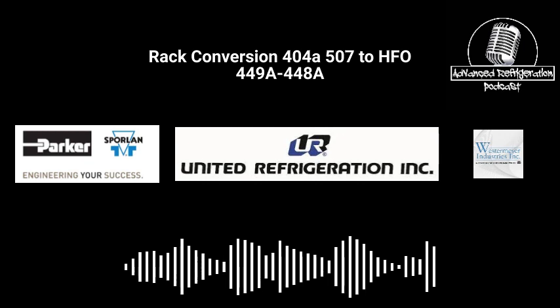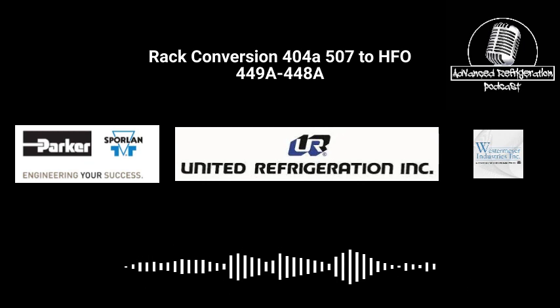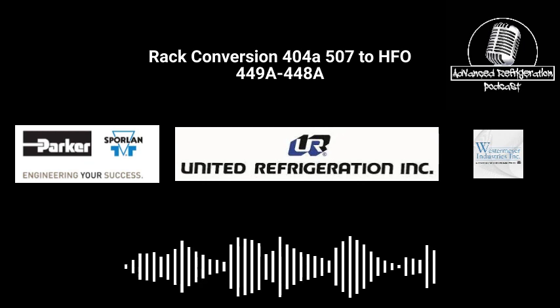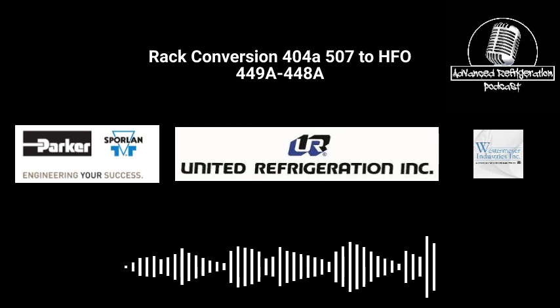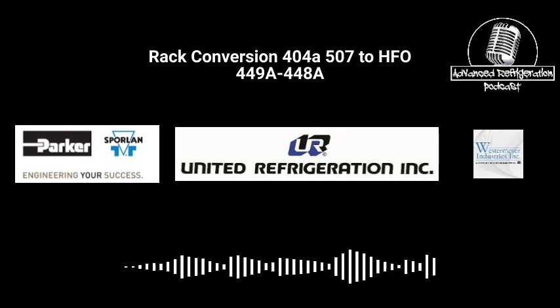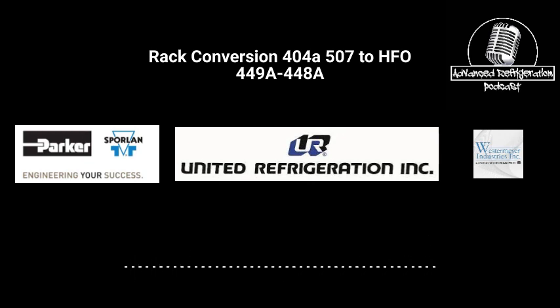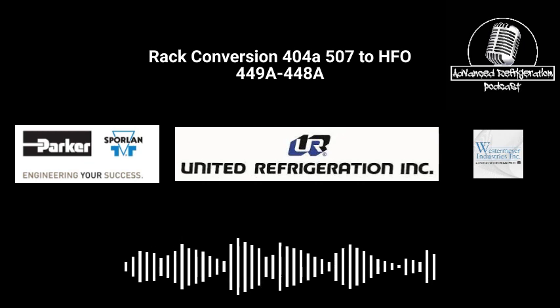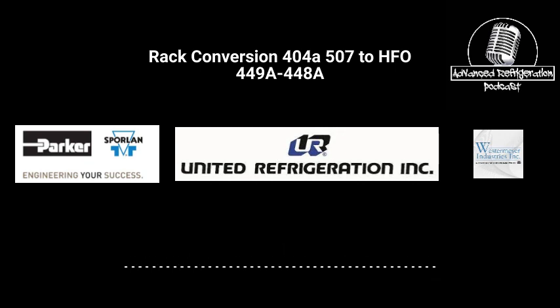They're getting cut out. By the time you unscrew the bottom and put the adjustment stem on there, the thing's been running for 10 years with a strainer that's half plugged. It's already warm. So screw it, it's getting Q bodies. And by the time you waste the time with that, a fitter could have already burned in 3 of them. And then say one leaks, you have to pump it back down. I would rather just cut the dryer out of the case, hard pipe the dryer, and leave the strainers in there, because I'd much rather clean a strainer than cut a dryer out.